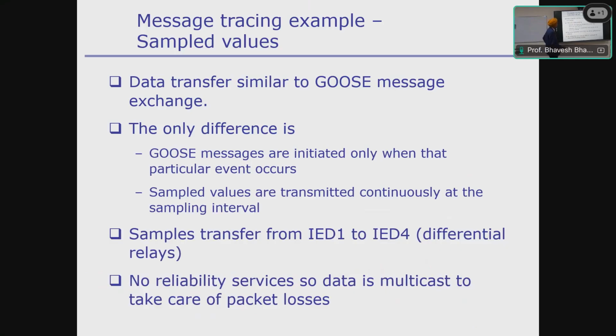Sampled values are similar. The only difference is sampled values are transmitted continuously, whereas GOOSE is only initiated by somebody, and there is no... well, in GOOSE you can multicast—you can send the same message again and again.